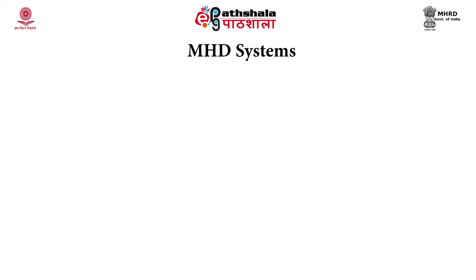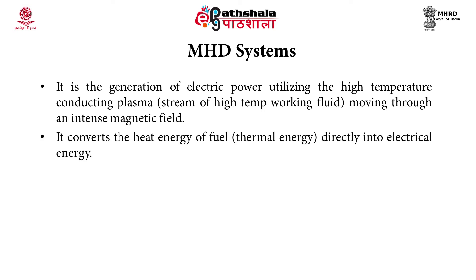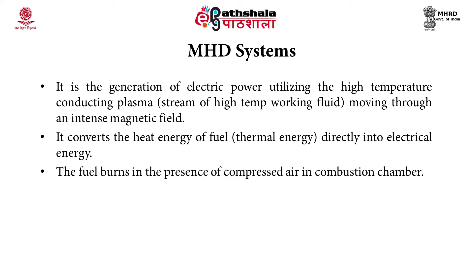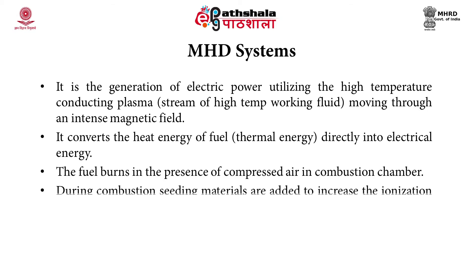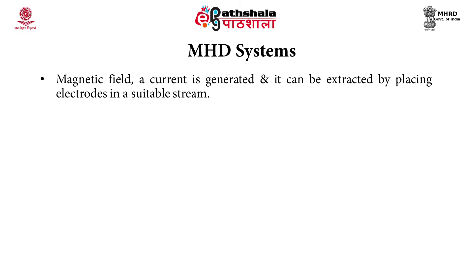MHD systems generate electric power utilizing high-temperature conducting plasma — a stream of high-temperature working fluid — moving through an intense magnetic field, converting thermal energy of fuel directly into electrical energy. The fuel burns in the presence of compressed air in a combustion chamber. During combustion, seeding materials are added to increase ionization, and the ionized gas is made to expand through a nozzle into the generator, where a current is generated and extracted by placing electrodes in a suitable stream.